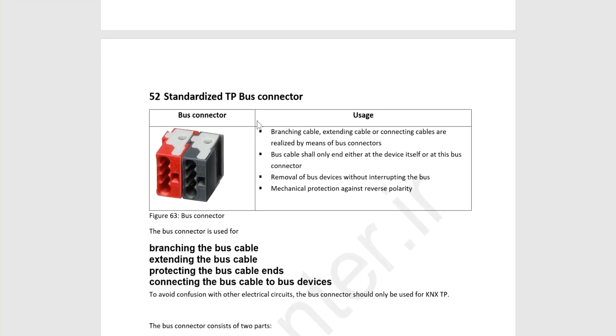Important things about the KNX connector. When we use the KNX connector, it is used to branch cable, okay? Extending cable or connecting cables are realized by means of bus connector.